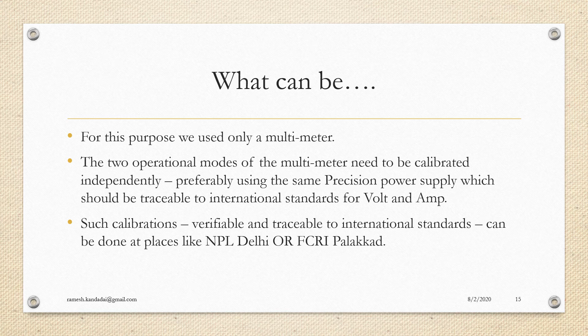So what we can do is to take certain primary standards. For instance, if you calibrate the precision power supply and keep it properly in calibration, maintain the record of the calibration and recalibrate it every time the validity of the calibration is about to expire, that itself can suffice to help us do the calibration for other things.